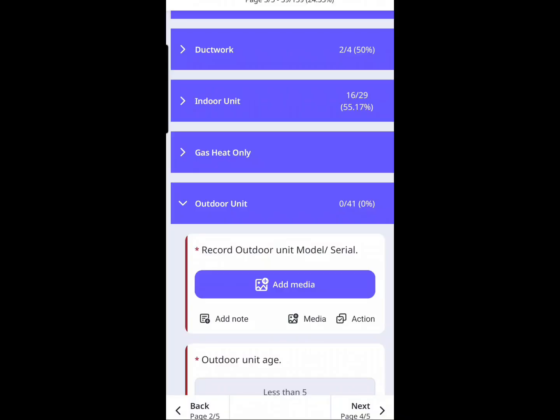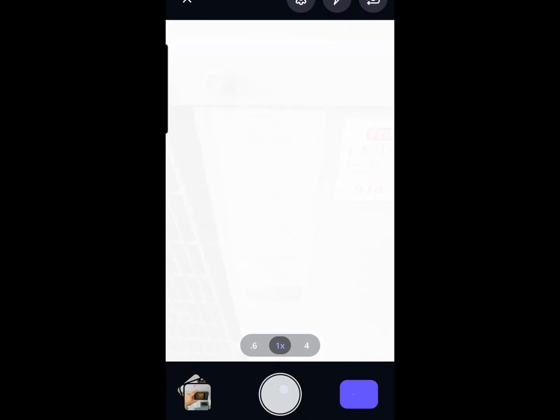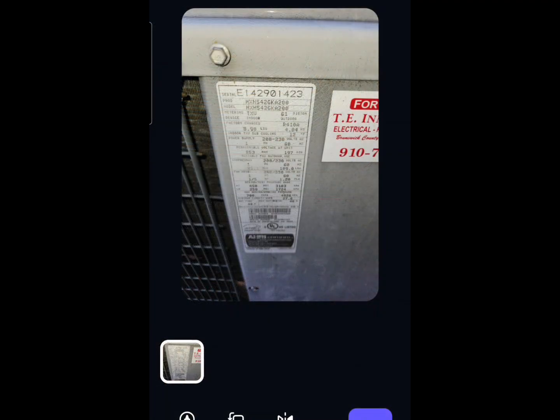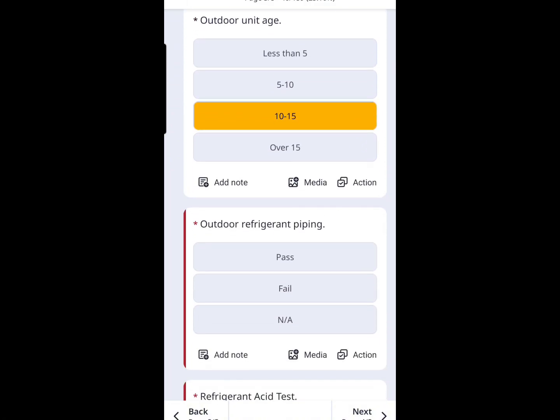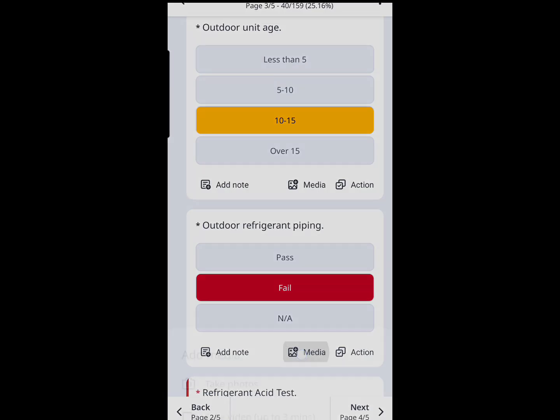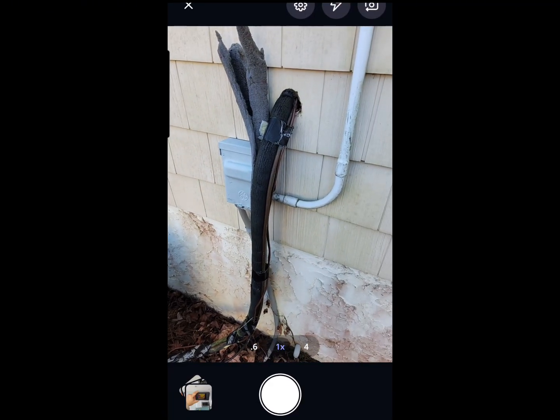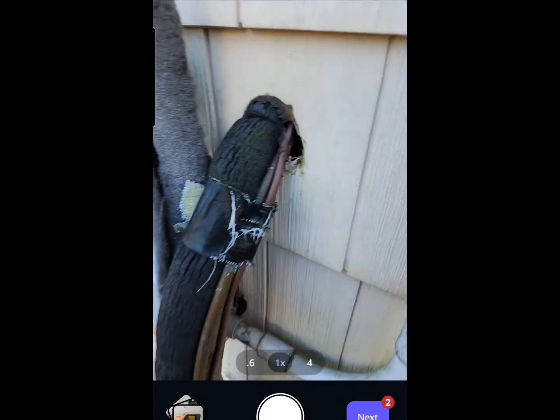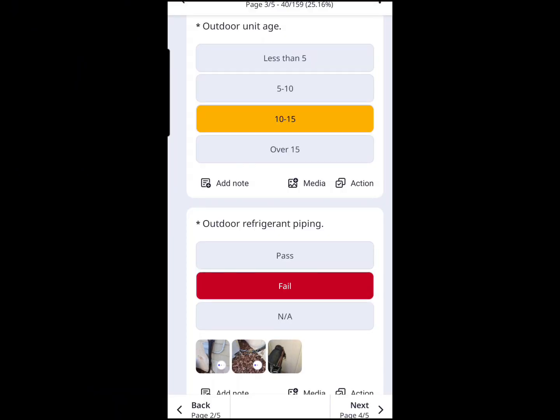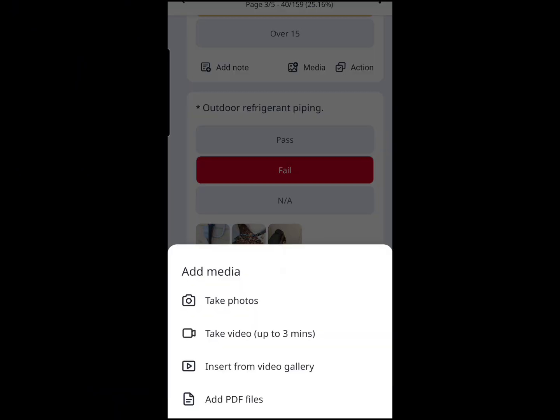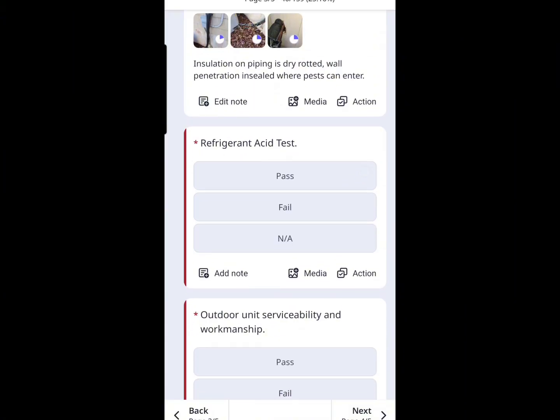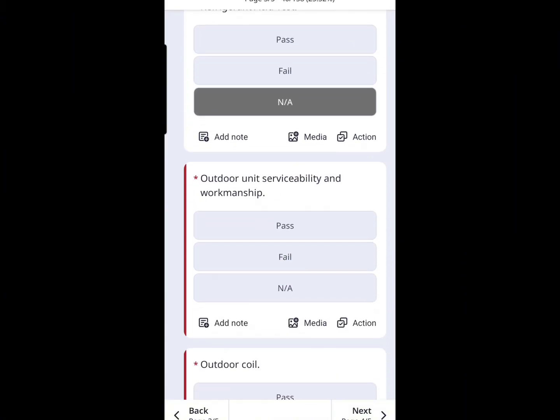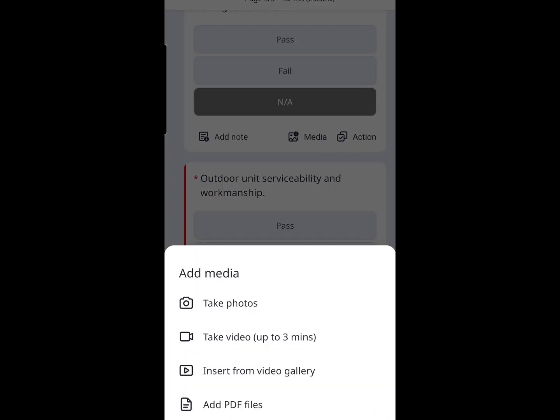There's an outdoor unit section to this checklist — very similar to the indoor unit. We first get the model number, grab some photo documentation, and record the unit age and condition — it's the same age as the indoor unit. Then we start looking at components. On the refrigerant piping, I put a fail because we've got some insulation issues and a penetration that's not sealed. We make a note of that and continue with the checklist — it gets red flags with an explanation in the notes. Normally I do a refrigerant acid test, but I ran out of those kits, so that gets NA.